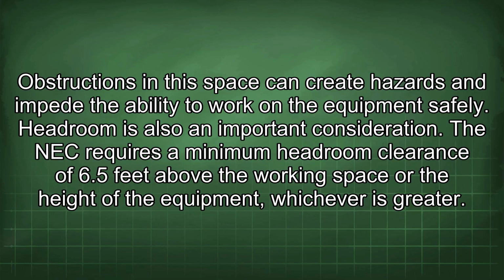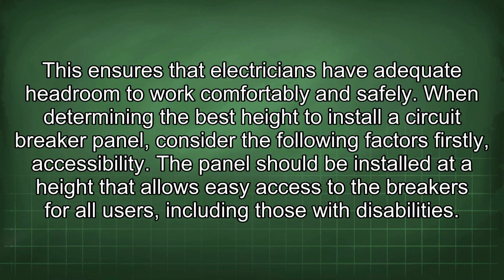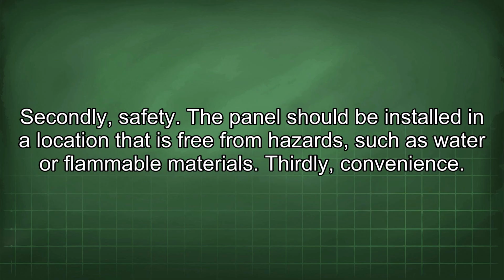Headroom is also an important consideration. The NEC requires a minimum headroom clearance of 6.5 feet above the working space or the height of the equipment, whichever is greater. This ensures that electricians have adequate headroom to work comfortably and safely. When determining the best height to install a circuit breaker panel, consider the following factors. Firstly, accessibility. The panel should be installed at a height that allows easy access to the breakers for all users, including those with disabilities.